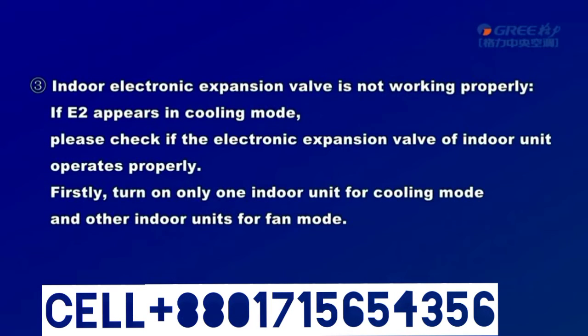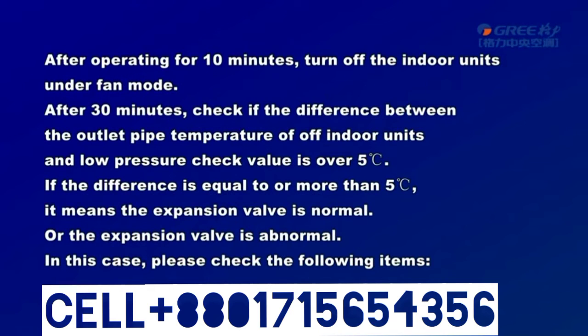3. Indoor electronic expansion valve is not working properly. If E2 appears in cooling mode, please check if the electronic expansion valve of indoor unit operates properly. Firstly, turn on only one indoor unit for cooling mode and other indoor units for fan mode. After operating for 10 minutes, turn off indoor units under fan mode.